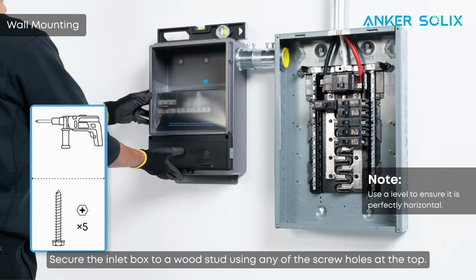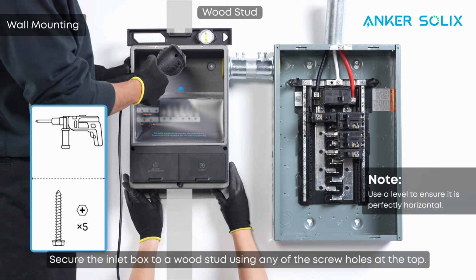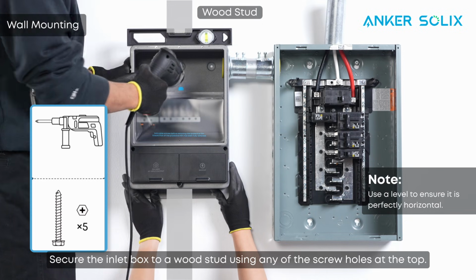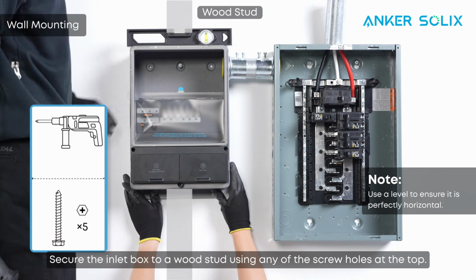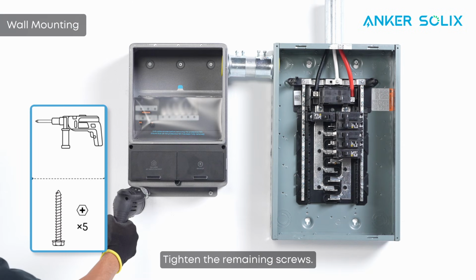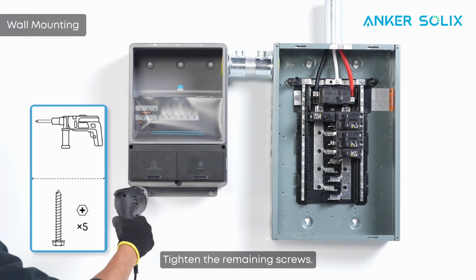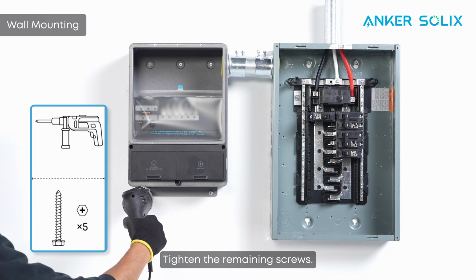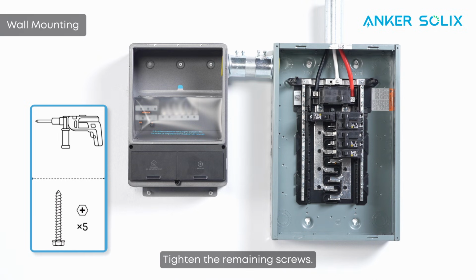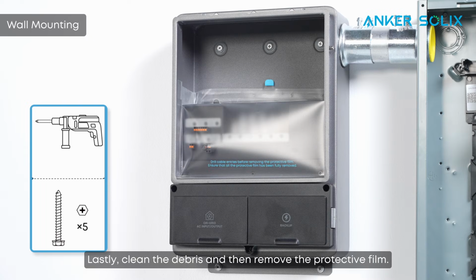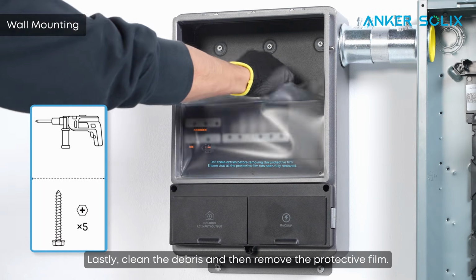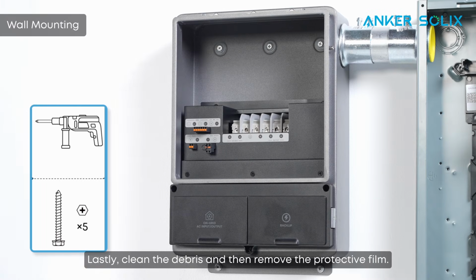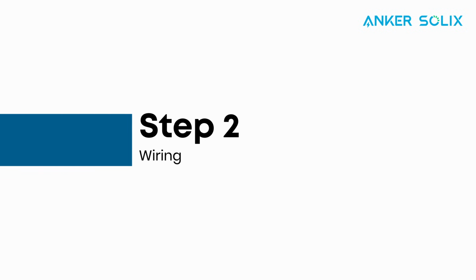Secure the inlet box to a wood stud using any of the screw holes at the top. Tighten the remaining screws. Lastly, clean the debris and then remove the protective film. After installing, here's how you set up the electrical connections.